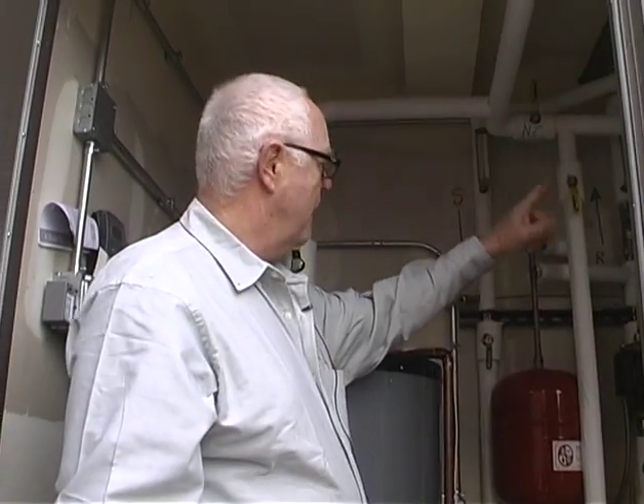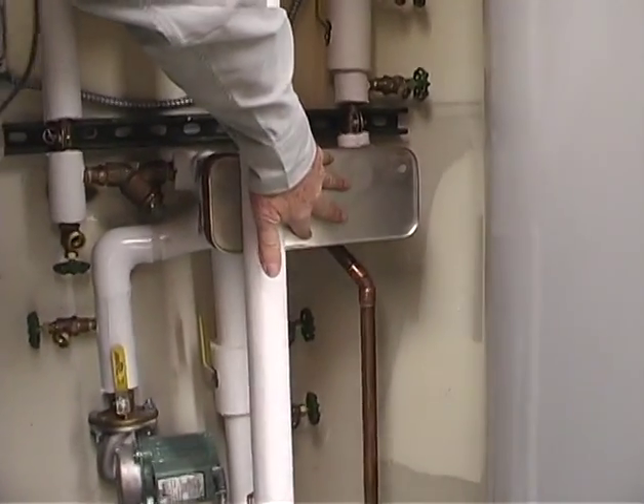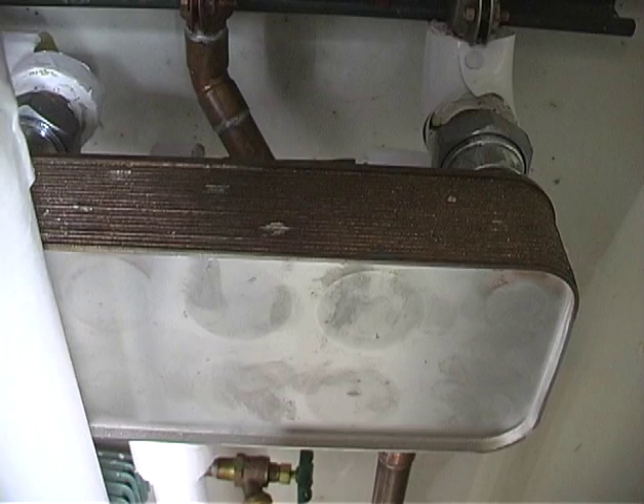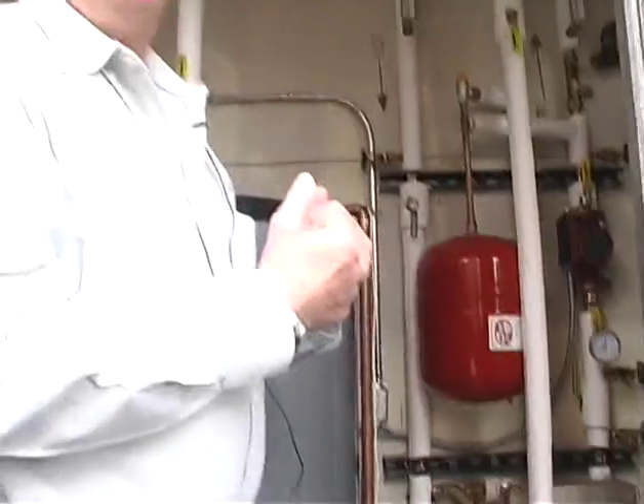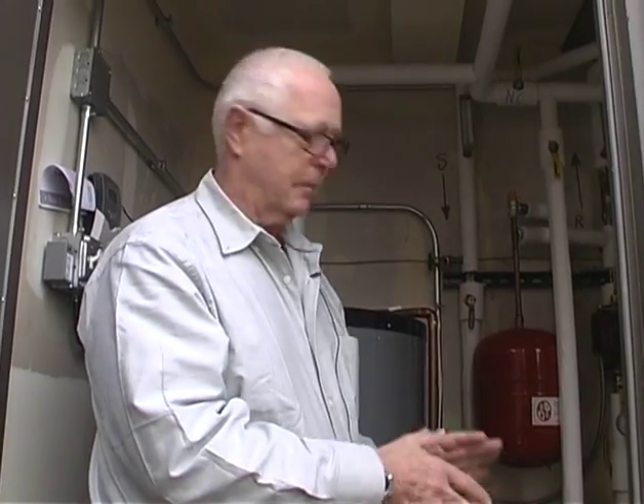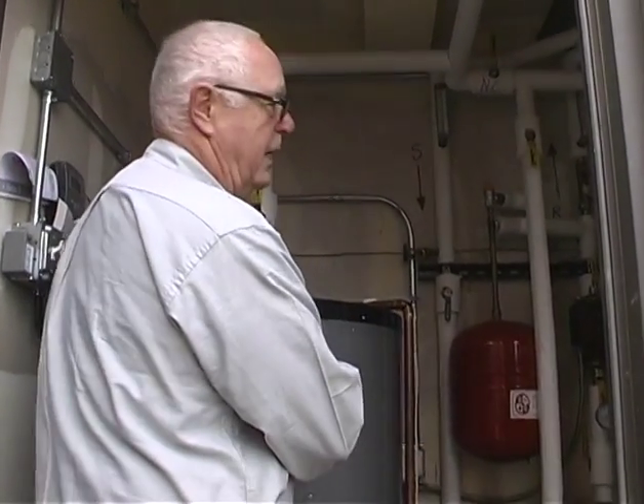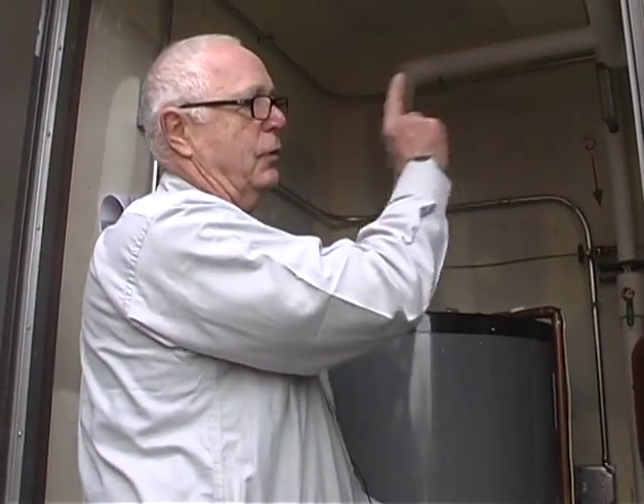The system we have here is basically called a closed loop system. It's pressurized glycol that goes all the way from the panels, where the sun hits it, and comes down here into this solar heat exchanger. The main function of the heat exchanger is to take the heat from the glycol and transfer it into the normal water that comes in, and then it puts it into this tank, and from this tank it goes to the boiler.